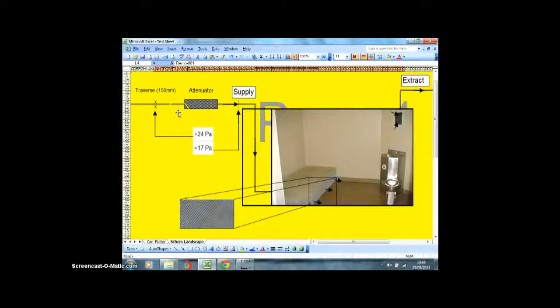I haven't included the actual primary ductwork coming from the AHU. That's not important at this point, but what is relevant is the configuration of the ductwork that leads down into the holding cells. It was quite cramped, and most of the ductwork didn't really have the best route to each cell. I think there were only 1 or 2 cells which had quite a good run, where I could obtain a correction factor and a traverse point and a test point just before it disappeared down into the wall. The difficulty with balancing the system was that it was not easy to measure the flow rate coming out of each cell.